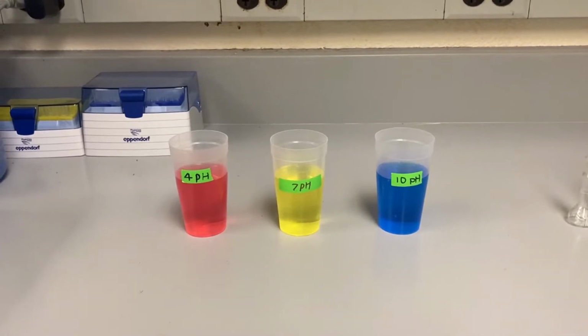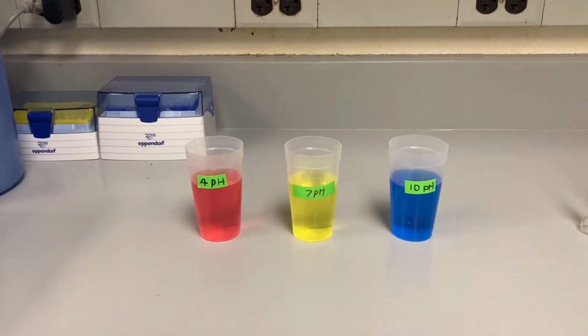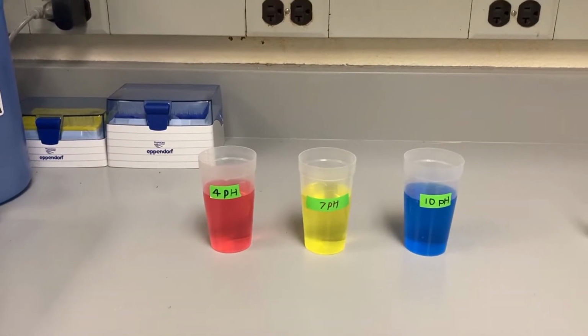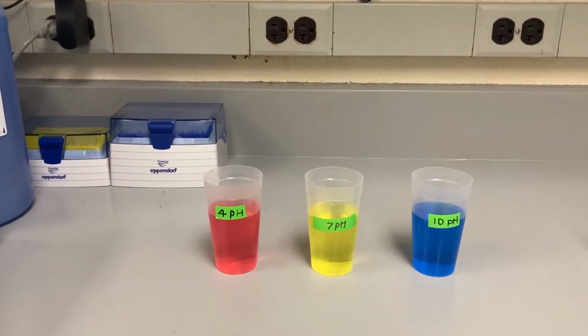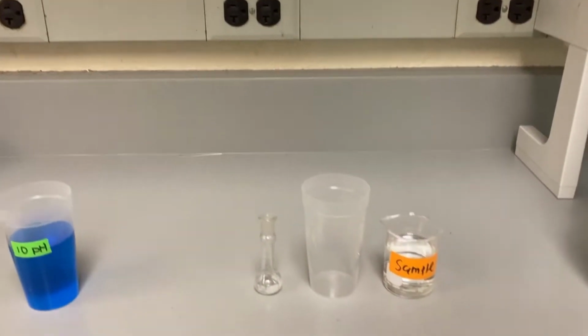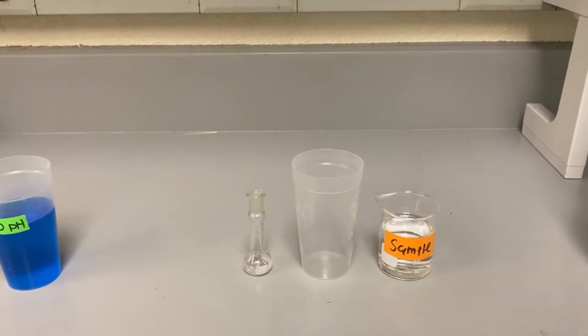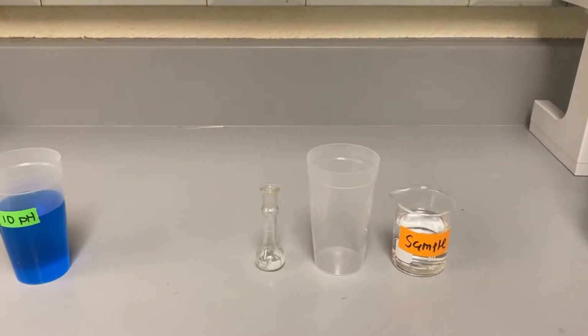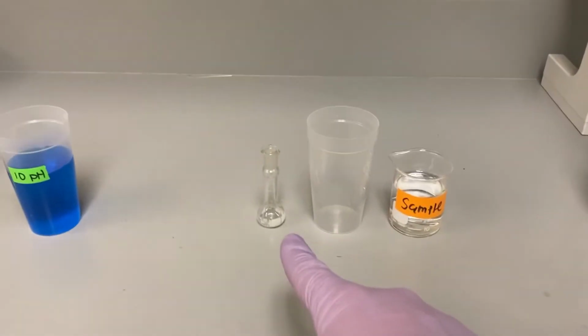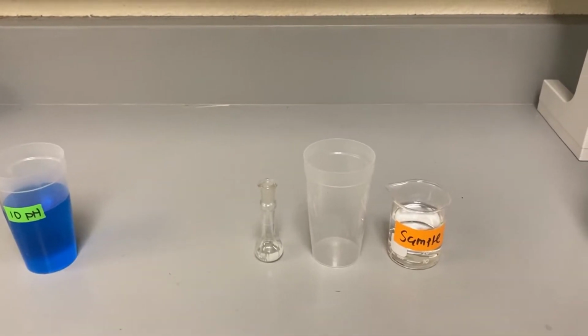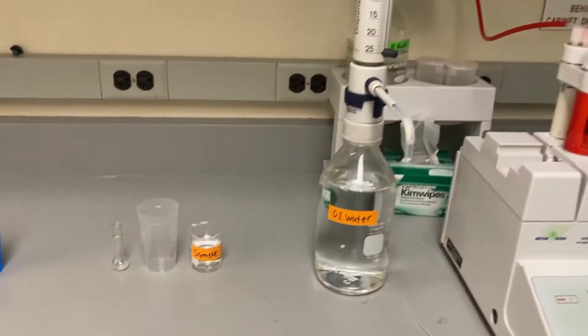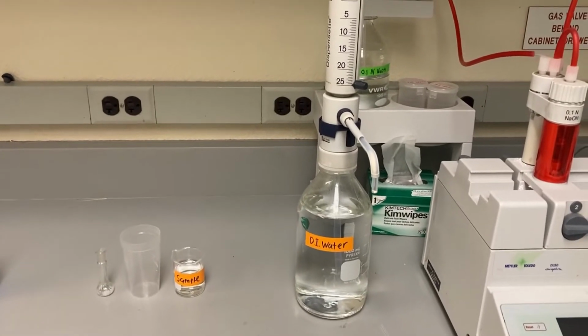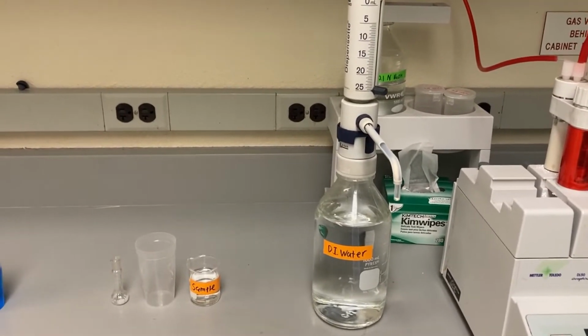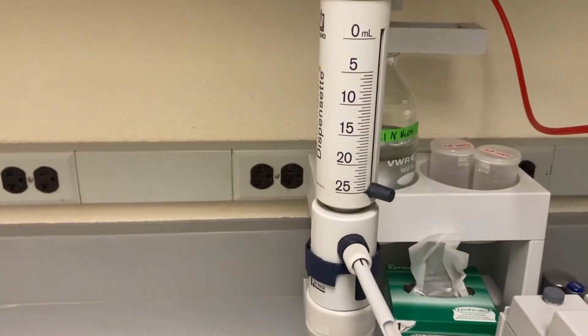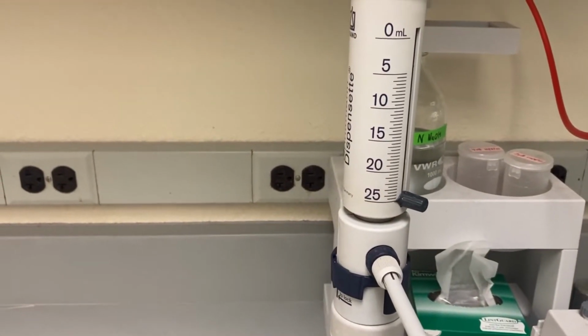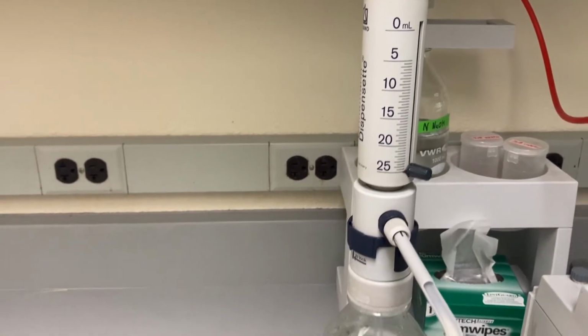To use the AutoTitrator to test TA in wine, you will first need to have a pH buffer at 4, 7, and 10, and then prepare your sample, whatever you're going to test, with a sample cup. And you'll need a 5 milliliter volumetric flask. And I would recommend having a Dispensette with DI water. One that can do 50 milliliters is recommended, but I only have a 25 milliliter.